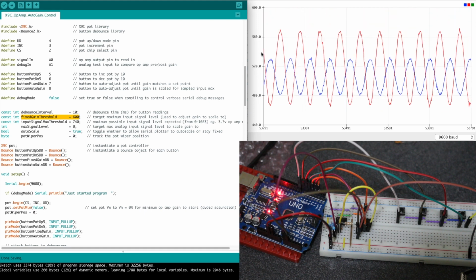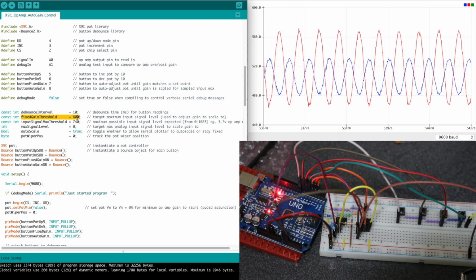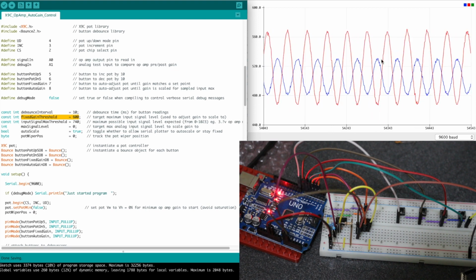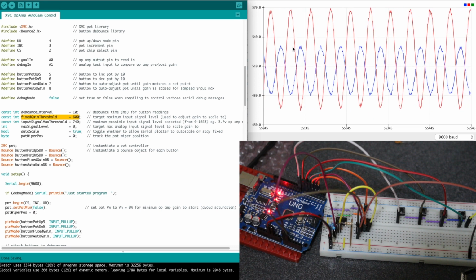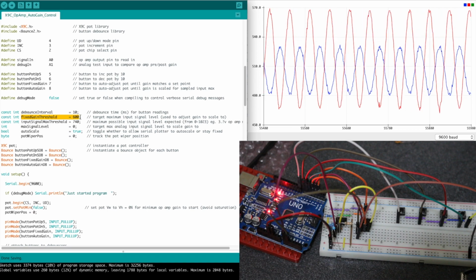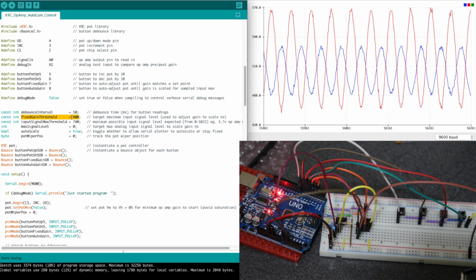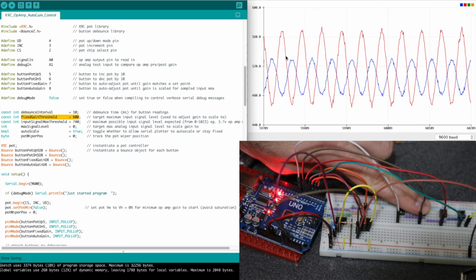So if I were to push the button for fixed gain target of 600, this waveform is going to pause because I'm going to stop plotting and then I'm going to recalibrate and set the gain so that this blue trace is going to try to get its peak close to 600 but without going over, because that's our threshold, meaning it's too high. We want to be as close as we can below 600. So I'll push the fixed gain button.